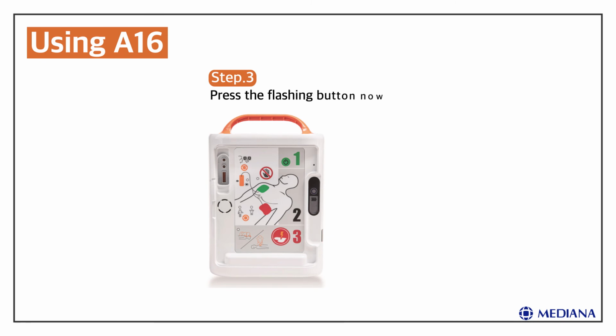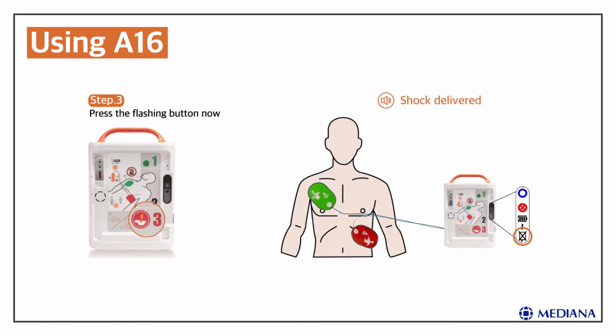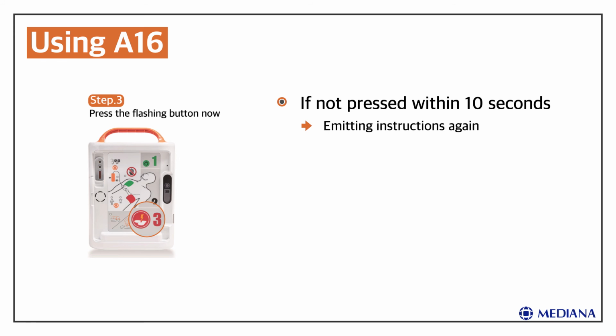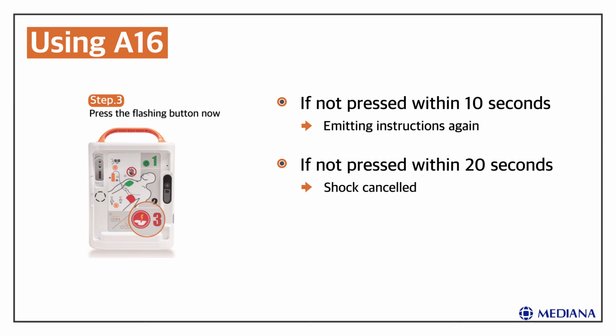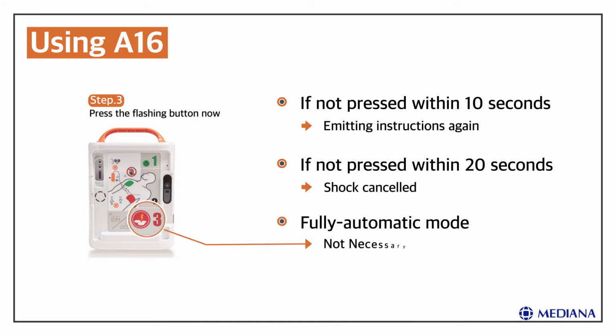Step 3, for semi-automatic mode: press the flashing button now. Shock delivered. If the shock button is not pressed within 10 seconds after the voice prompt, the instruction 'press the flashing button now' will be emitted one more time. If the shock button is not pressed for more than 20 seconds after the initial instruction, the AED moves on to the CPR process after the voice prompt 'shock cancelled' is emitted. In fully automatic mode, the shock will be delivered without needing to press the flashing button.